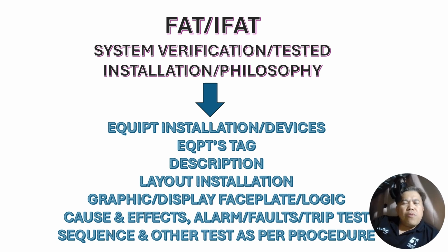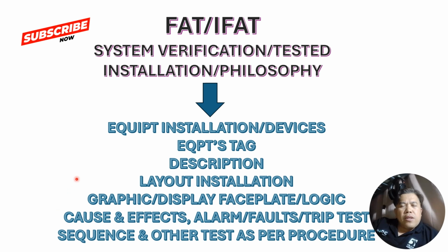So before we proceed with the installations, all the devices and equipment that you need to provide must go through testing, what we call FAT and IFAT. Meaning factory acceptance testing and also integrated factory acceptance testing. We do that in our vendor facilities, in order to verify the system and check the philosophy of your system.